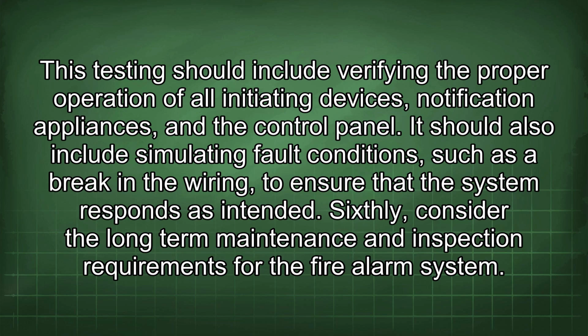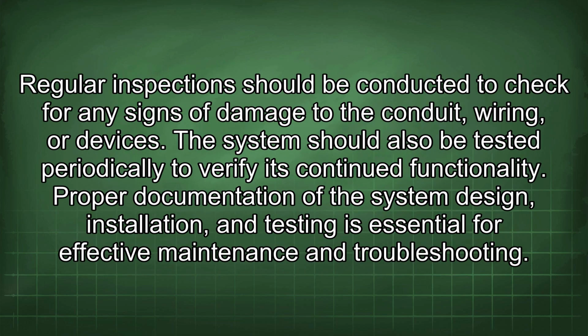as intended. Sixthly, consider the long-term maintenance and inspection requirements for the fire alarm system. Regular inspection should be conducted to check for any signs of damage to the conduit, wiring, or devices. The system should also be tested periodically to verify its continued functionality. Proper documentation of the system design, installation, and testing is essential for effective maintenance and troubleshooting.